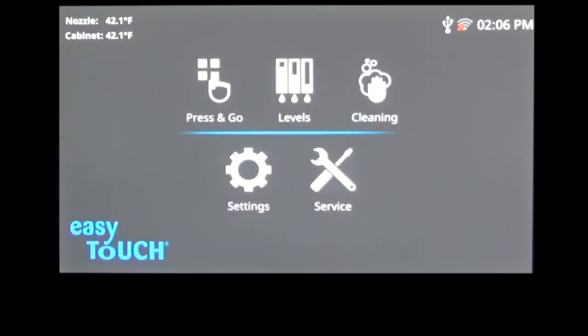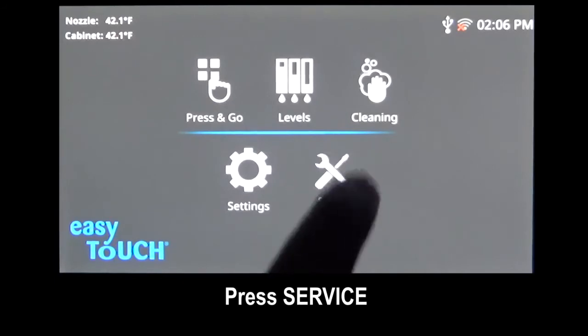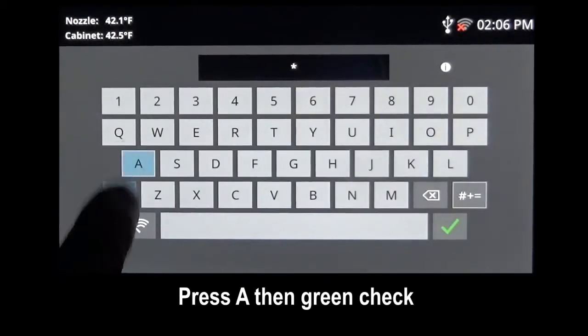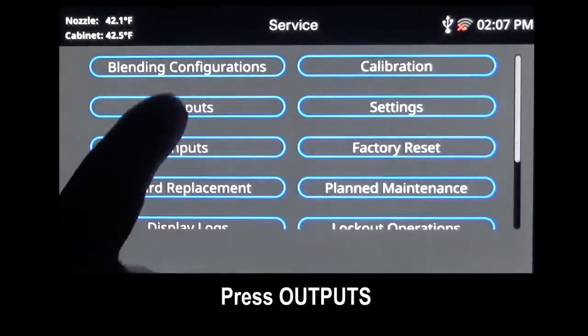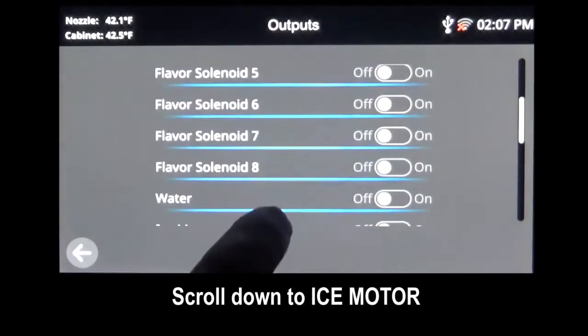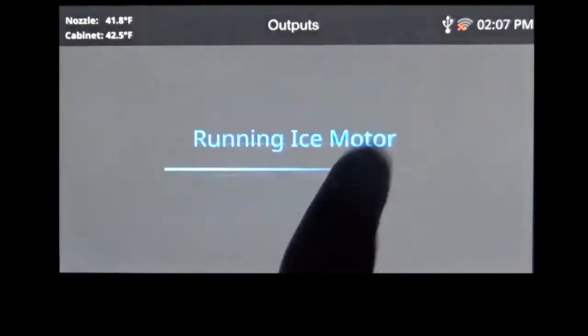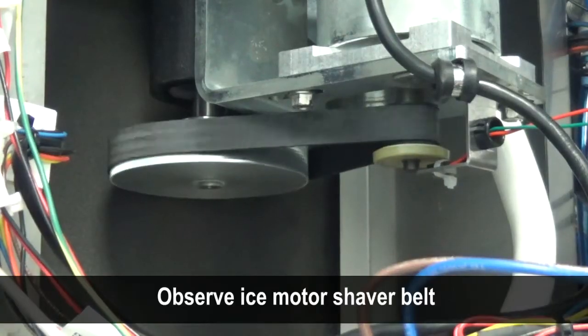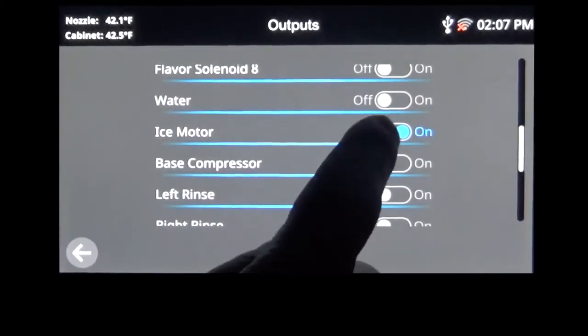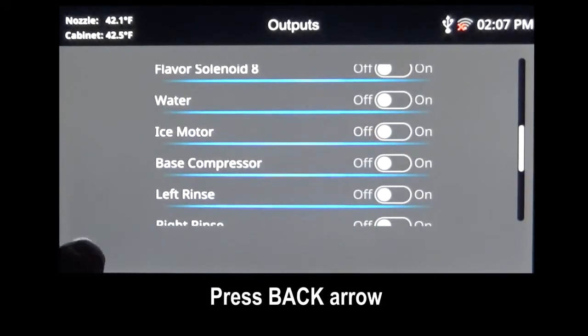For Common Controller screens, start at the Easy Touch and press Service. Press A, then the green check. Press Outputs. Scroll down and change ice motor state to On. Observe the ice shaver belt operation. Wait 10 seconds, then change ice motor state to off. Press back arrow to return to Easy Touch screen.